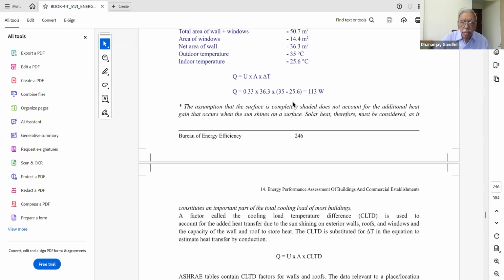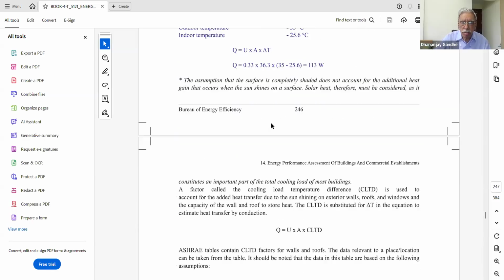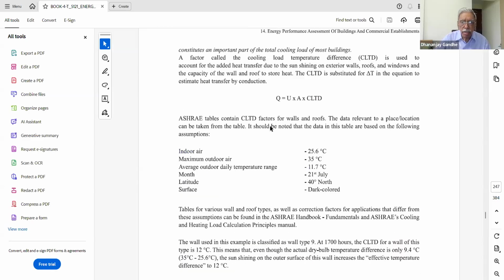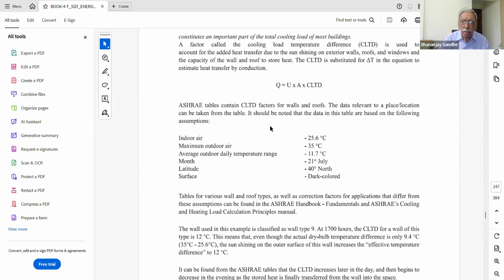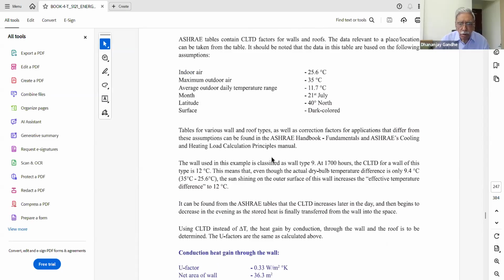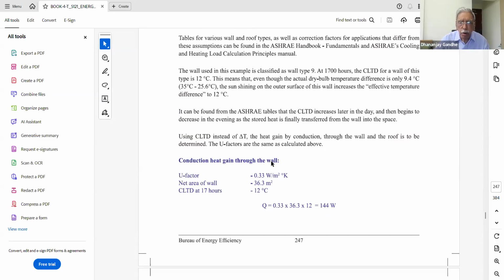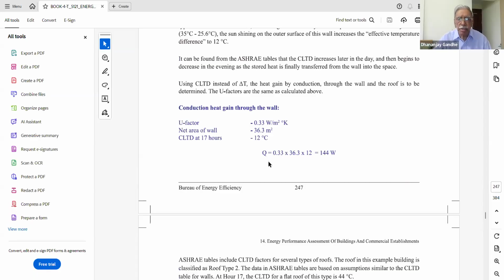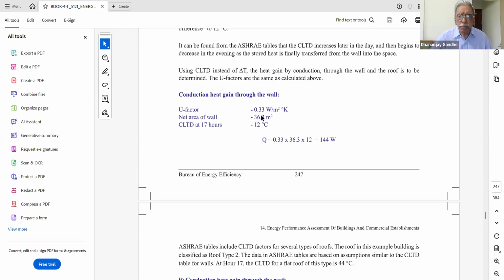So this is the heat gain through the wall. Similarly, heat gain through other components also can be calculated. ASHRAE gives some CLTD factors; those can be used for further calculation.